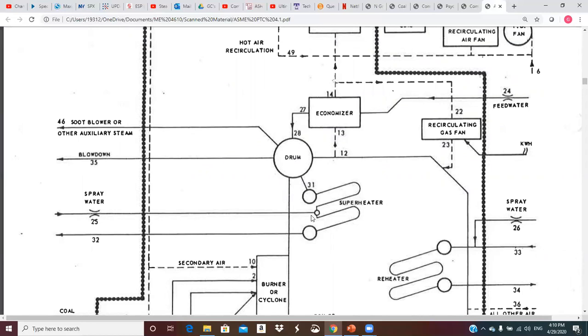We're going to come down and feed the steam generation circuits out of the bottom of the boiler. If it's forced or pumped circulation, we'll go around this loop. It's going to come up through here. This is where the steam is generated. And then we'll come back up into the boiler here, or into the drum for separation. And then the saturated steam would come out at 31, go through superheaters. This would be an attemperator for spray. Then we go to the primary superheater first, and then to the secondary superheater, and then out to the turbine.